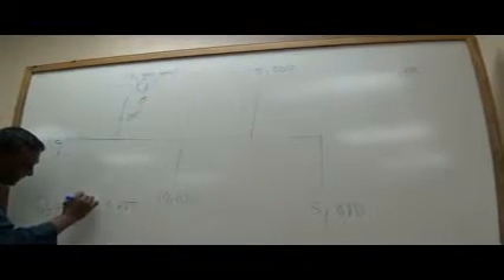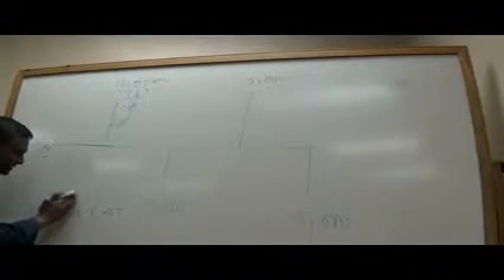If you remember, it's the Q equation. Q equals 500 times GPM times delta T. There's something you left out. CFMs? No, GPM, sorry, it's water. If you have that, I can calculate how many gallons a minute I need to get out there, and that's going to tell me whether this pump is working.